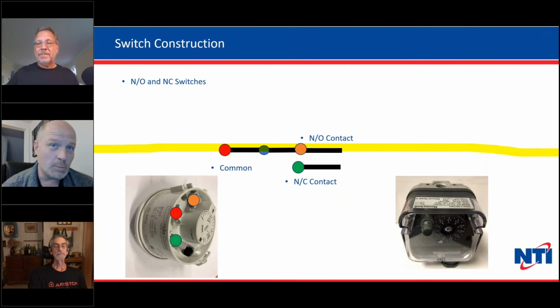And what you want to do is, to Steve's point, if you look at the face of these switches, embossed into the plastic on the face of this Honeywell switch on the right-hand side here, there's actually a wiring diagram, and it'll say NO, NC, and C. C stands for the common, which means that it's the one that connects to one of the other two. And then the normally open is the one that's going to close, and the normally closed is the one that's going to open. So always keep an eye out for those diagrams, because they typically are there on anything that's a dual acting switch like this.